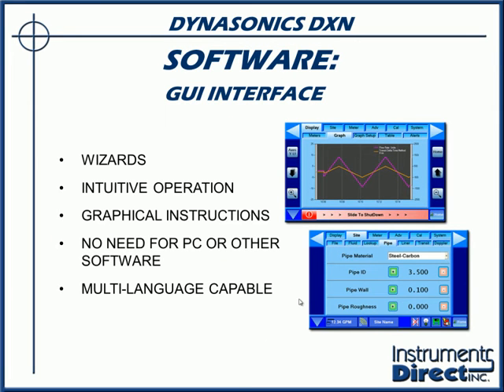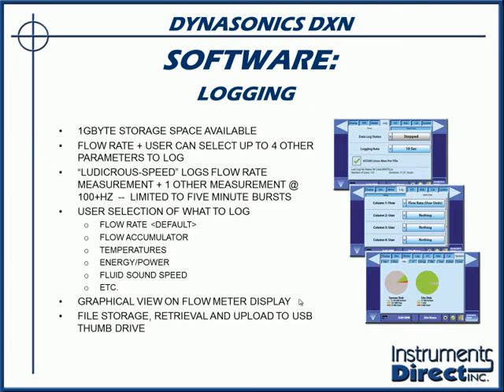Well, when's the last time you heard the word GUI interface for an ultrasonic transit time or Doppler flow meter? As we said, this device is very intuitive. It has a setup wizard and graphical instructions. There is no need for a PC or any other software, and it has multi-language capabilities. As far as the logging functions, we'll get into that a little deeper, but it can store up to 1 gigabyte with an onboard SD card, and you download that with a USB cable.